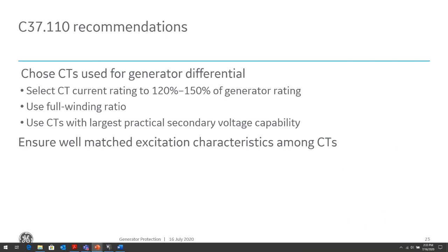And you want to use CTs with the largest practical secondary voltage capability, meaning the excitation voltage should be as high as possible. So when we rate CTs, the IEEE rating is usually C800, C400, C200, and the numbers behind the C are basically the secondary voltage capability. So C800 will be able to handle as much as up to 800 volts across the CT terminal and be able to reliably convert the primary current to secondary current.